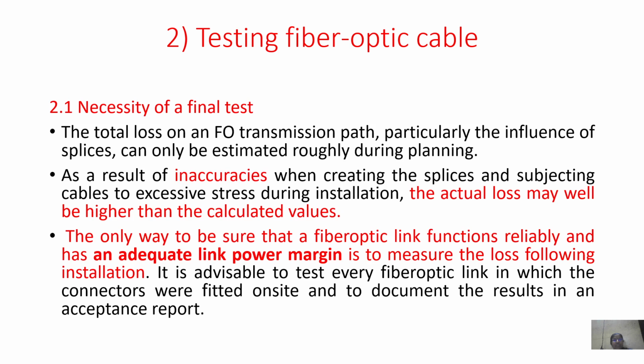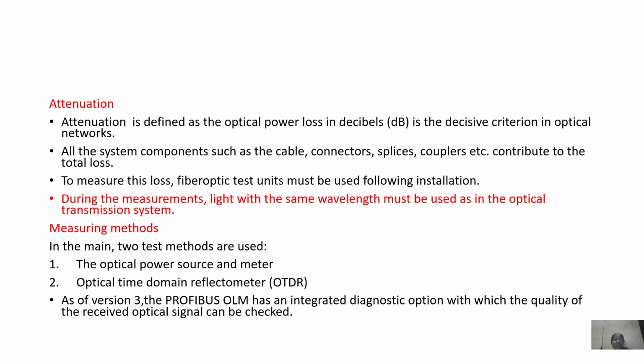So testing the fiber optic cable. The actual loss may be very high compared to the calculated values when using the fiber optic cable in Profibus communication. So there are two ways of testing this. One is the optical power source meter and the other is the optical time domain reflectometer.